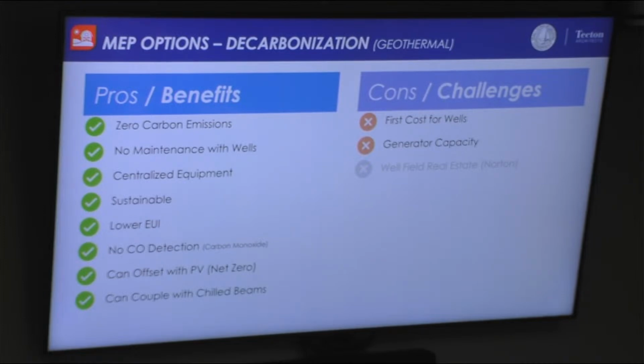We have enough, what does a well field look like on a site? That's what I was going to ask. The well field, you won't see anything, it'll be grass, it'll be on the parking lot. What does the array look like? The array is typically done on a 20 by 20 array, 20-foot stagger. What you do is take a 20 by 20 array and offset it 10 feet, so you get staggered wells. It gives you much more efficiency between the wells. That's the minimum you want to use for a well field dimension.